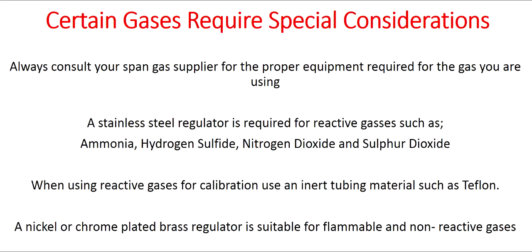A stainless steel regulator is required for reactive gases such as ammonia, hydrogen sulfide, nitrogen dioxide, and sulfur dioxide. When using reactive gases for calibration, use an inert tubing material such as Teflon. A nickel or chrome plated brass regulator is suitable for flammable and non-reactive gases.